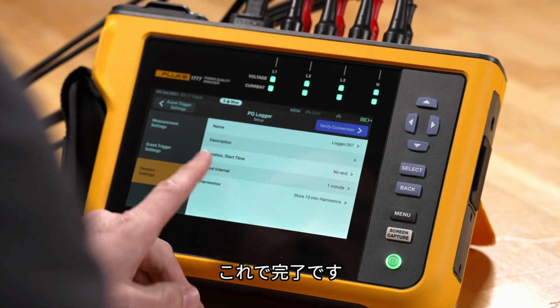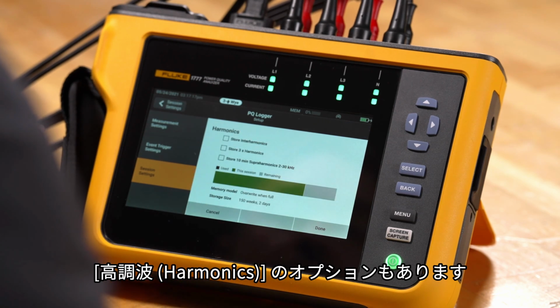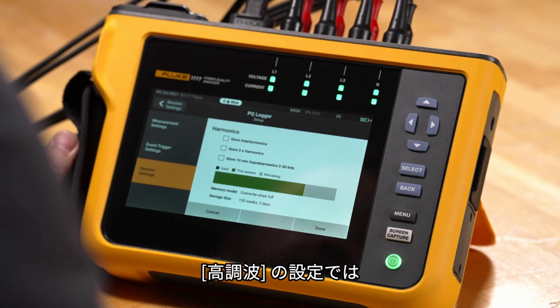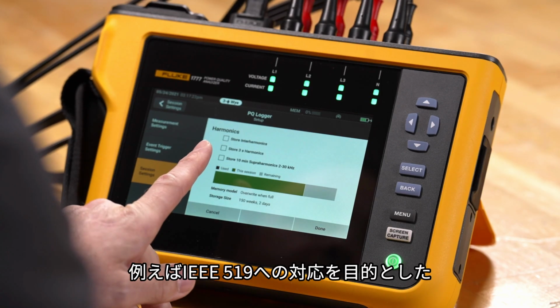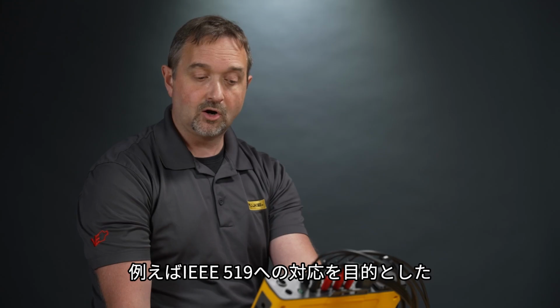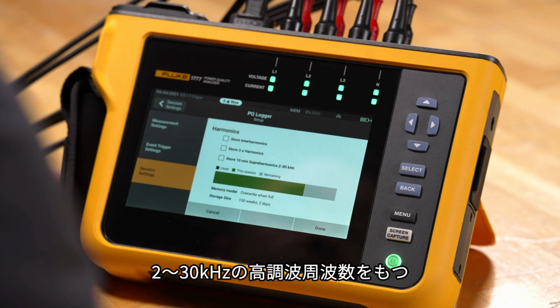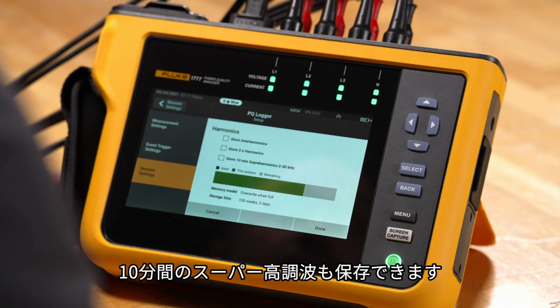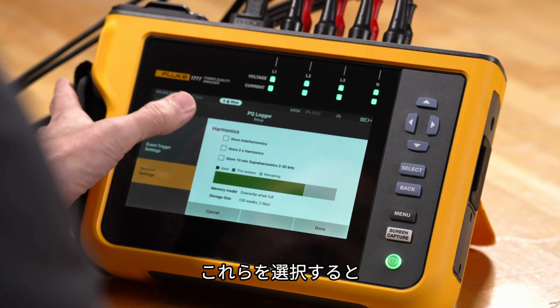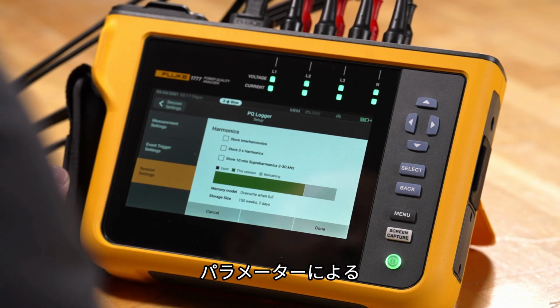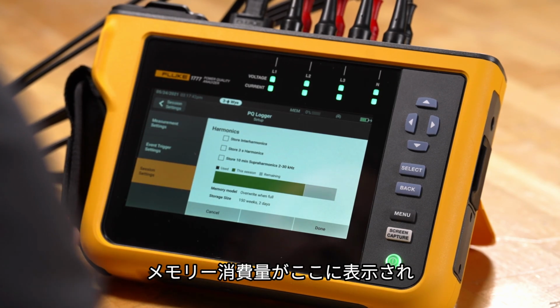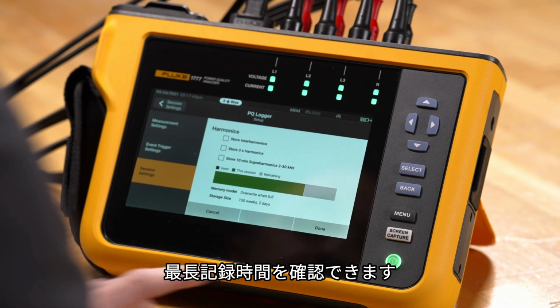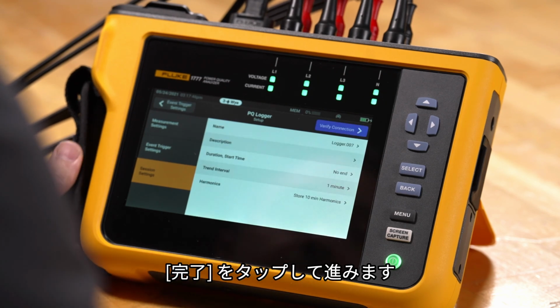So we're done here. We also have an option here, harmonics. For harmonics setup, we can store interharmonics. We can do 3-second harmonic data, which would be for IEEE 519 purposes as an example. We can also store 10-minute super harmonics, which are 2 to 30 kilohertz harmonic frequencies. Once we pick these, it'll also show us how much memory consumption is taking place from those parameters, letting us know the max record time. I'm going to tap done here.